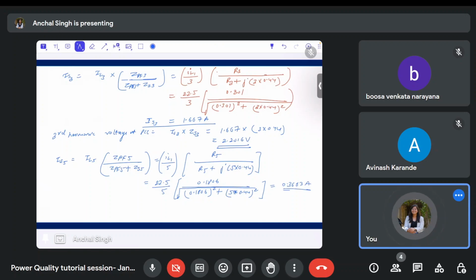Similarly, you can find Vs5 as IS5 into ZS5, the point of common coupling voltage due to the fifth harmonic component, which equals 0.3683 into 5 into 0.44, coming out to be 0.81 volts.